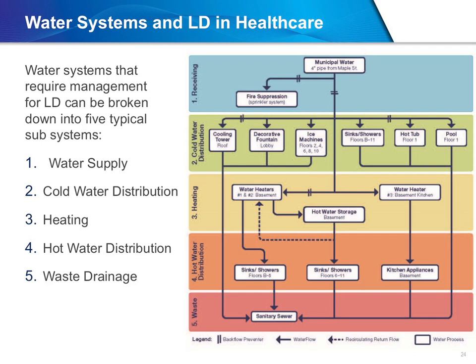Further, Legionella can grow in parts of building water systems that are continually wet and within a temperature range suitable for growth. Since a building water system contains many different subsystems and components, we will review some of the major ones, with a discussion of the relevant approaches to identifying Legionella hazards and control methods. Addressing each of these water quality issues at the source is the best way to assure that the water entering a facility does not have the potential to introduce or contribute to waterborne bacteria development and growth.